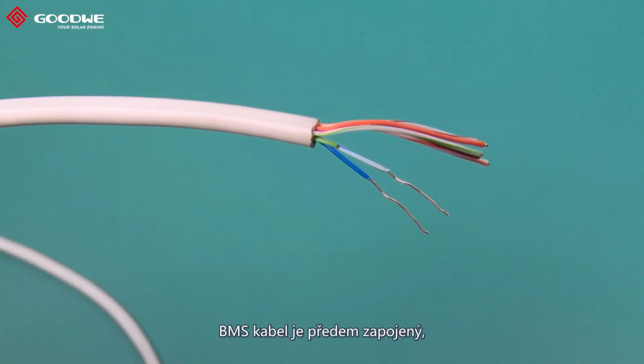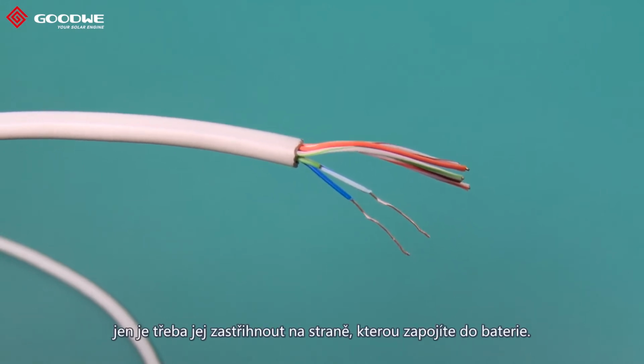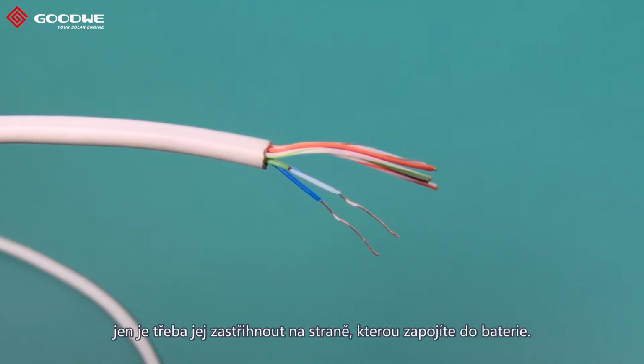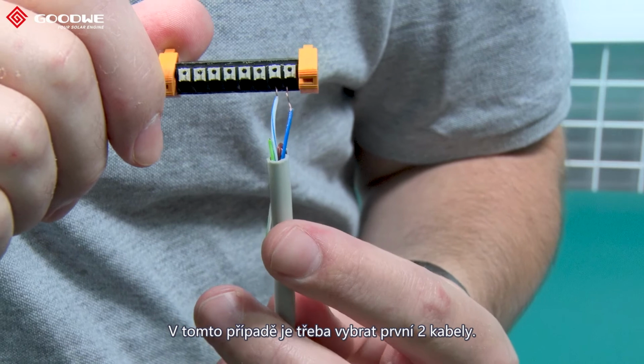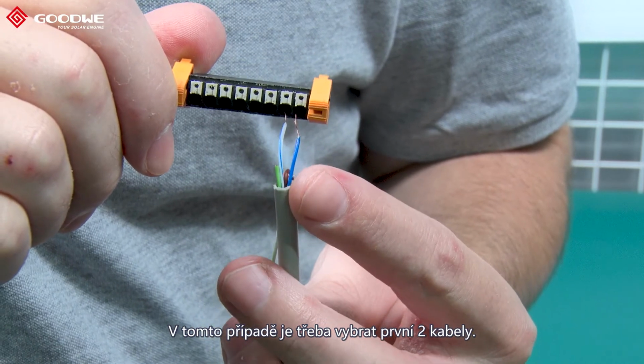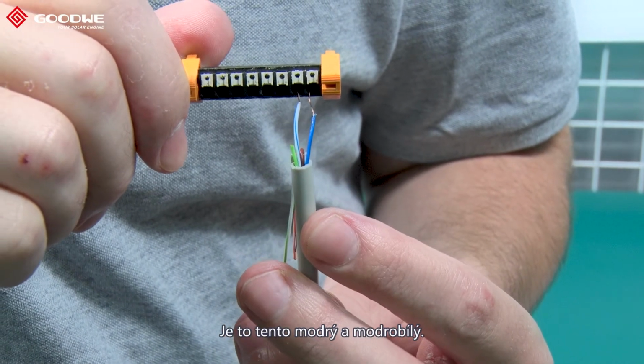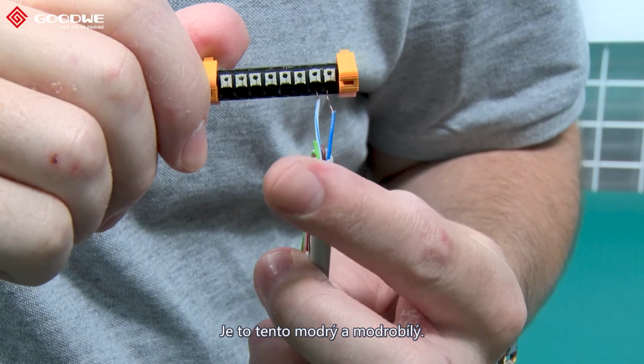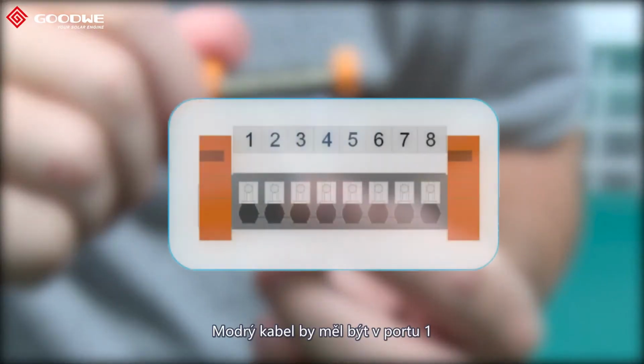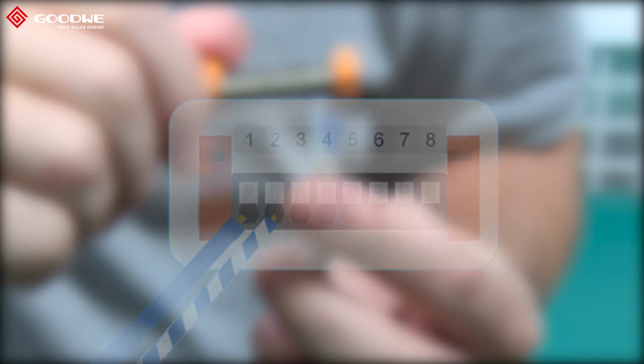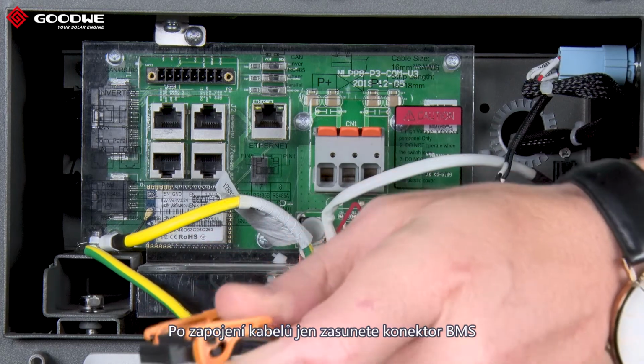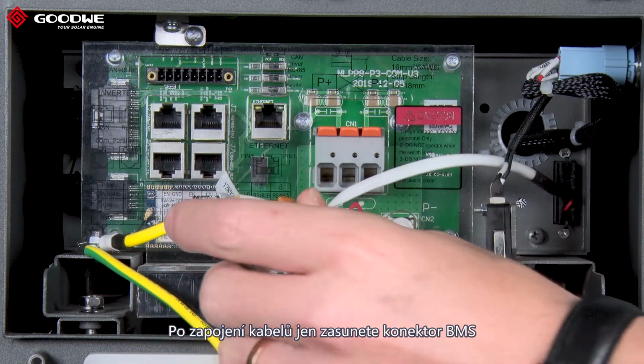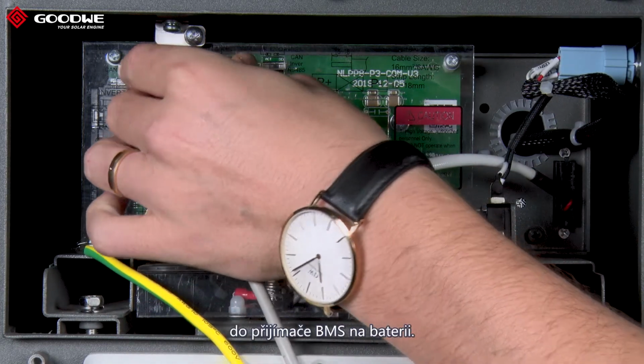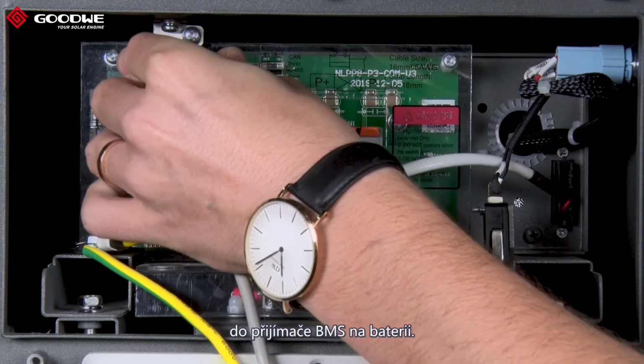The BMS cable comes pre-wired. You just need to cut the other side that connects to the battery. In this case, we need to select the first two wires over here, the blue one and another that is blue and white. You should have the blue wire in port 1 and the blue and white one in port 2, like so. Once you've got the wires in, you just place the BMS connector in the BMS receiver on the battery end, like so.